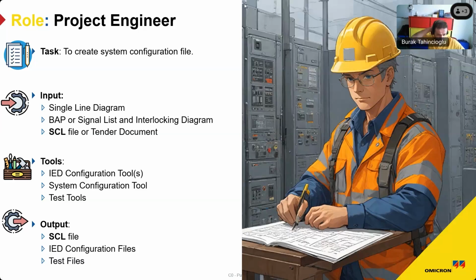The tool we would use in this case is the system configuration tool, the SCT, the abbreviation defined by the standard, to engineer the digital substation. Additionally, we could also have the IED configuration tools, not really loading to IEDs, but making the preparations for the commissioning engineer to configure the IEDs with proprietary tools.